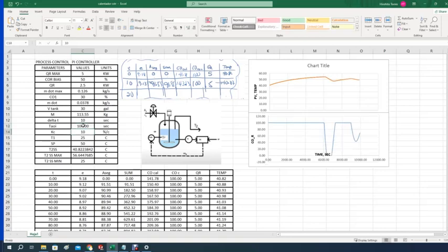More oscillation, and the bad thing is that from 100 it really dropped to 0, and then it took a while to get back to 100, and then it dropped back, but I still see a lot of oscillation, and that's not good. But let's keep doing this. From 100, how about 50? It's going to establish oscillation, and you are not going to get the set point that you want. It's going to oscillate a lot. Let's get one smaller, 25. See, no, not good at all.